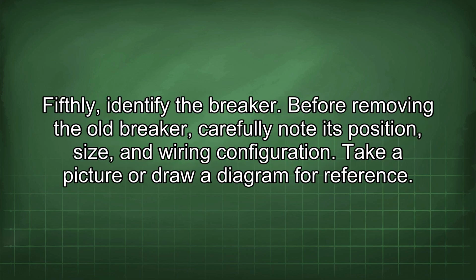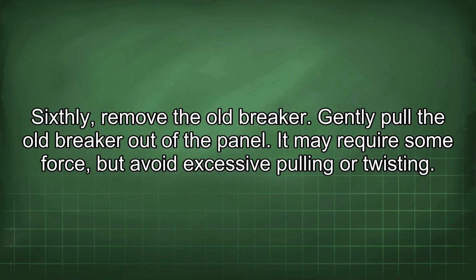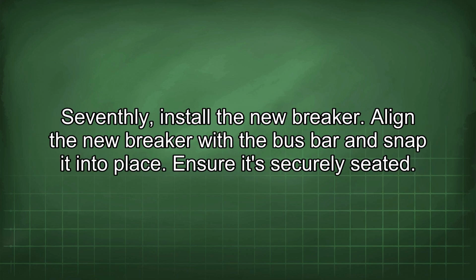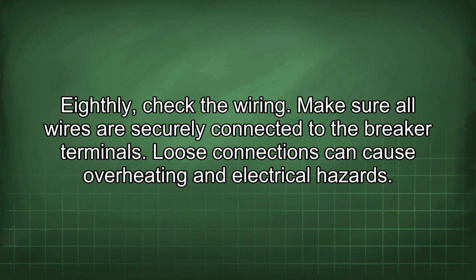Fifthly, identify the breaker. Before removing the old breaker, carefully note its position, size, and wiring configuration. Take a picture or draw a diagram for reference. Sixthly, remove the old breaker. Gently pull the old breaker out of the panel. It may require some force, but avoid excessive pulling or twisting. Seventhly, install the new breaker. Align the new breaker with the bus bar and snap it into place. Ensure it's securely seated.